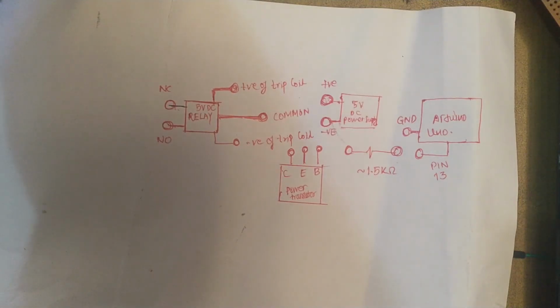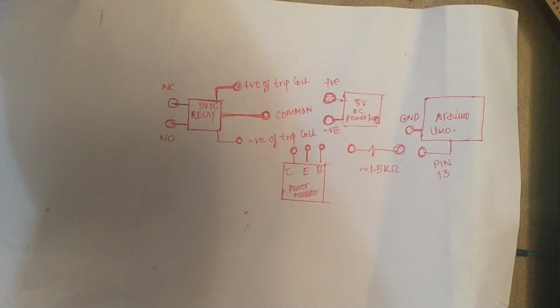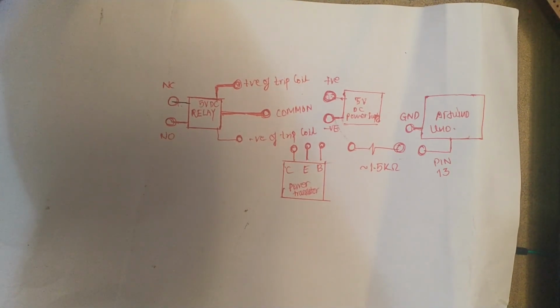We find from the resistance test that the pins A and B, C and F, E and F, G and H, and C and E are the candidate pairs for the primary terminals. We need to do the polarity test to determine which one of them actually is. Now for the polarity test, you need to develop a relay tripping circuit. You can also send a short pulse of DC voltage across the primary winding to determine the polarity, but this method is more efficient and yields better results.